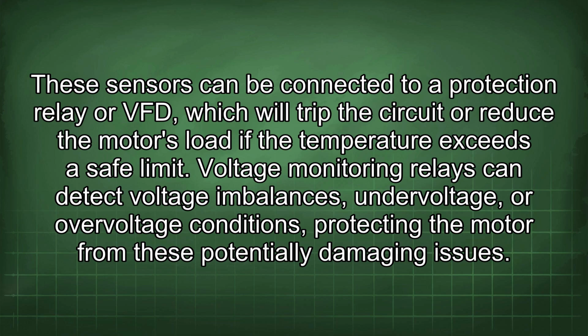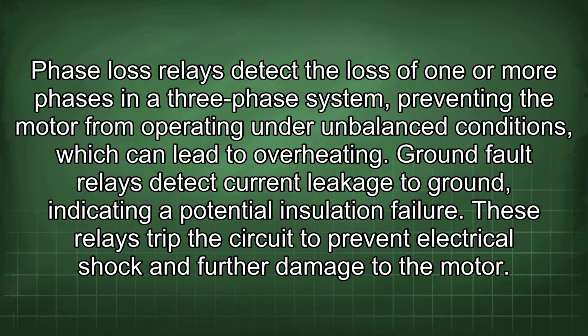Voltage monitoring relays can detect voltage imbalances, undervoltage, or overvoltage conditions, protecting the motor from these potentially damaging issues. Phase loss relays detect the loss of one or more phases in a three-phase system, preventing the motor from operating under unbalanced conditions, which can lead to overheating. Ground fault relays detect current leakage to ground, indicating a potential insulation failure.